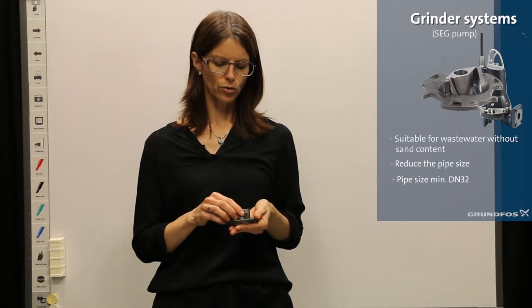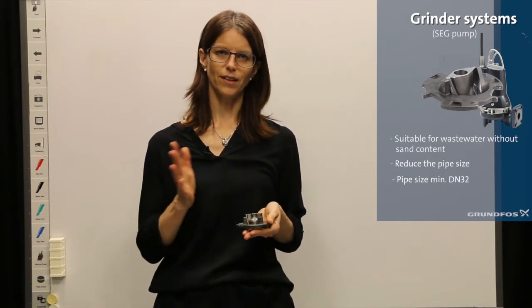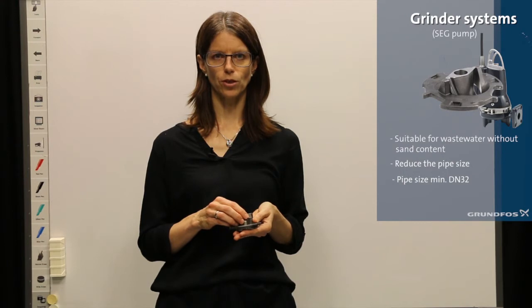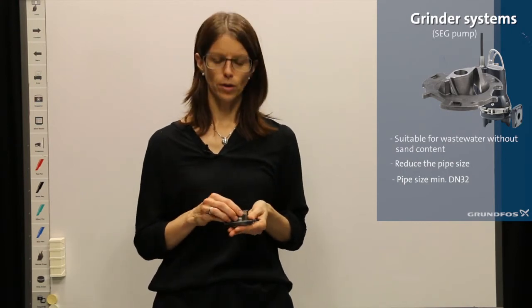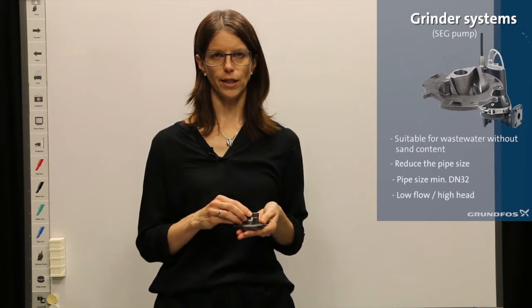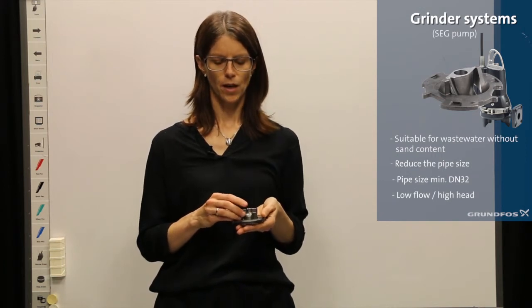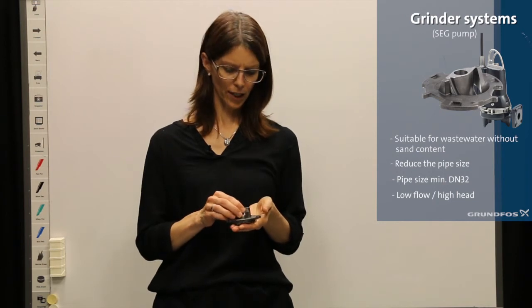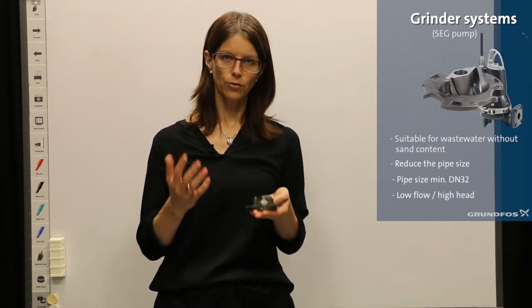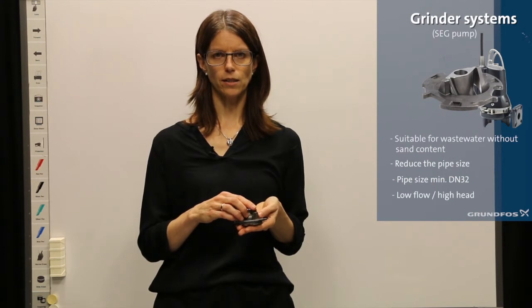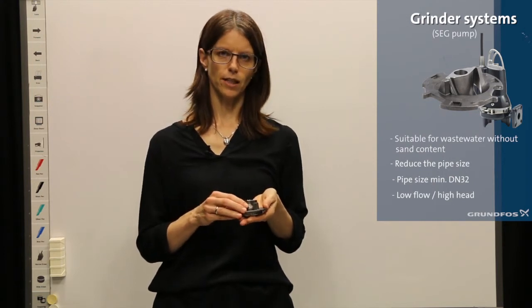You need to run the grinder pump not too far to the right on the performance curve — a maximum of about two liters per second. But this pump is very effective, and if you need to reduce pipe sizes in the system the grinder pump is the optimal solution.